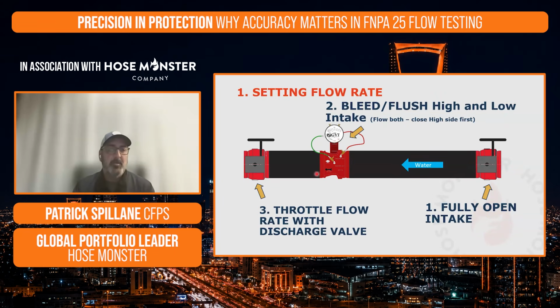But the way that we're going to set this flow meter up is that we're going to open up this intake valve 100%. It's going to be fully open, allowing water to fill the entire pipe diameter here. This valve is currently closed. As this valve is open, we're going to fill this entire unit with water. We're going to bleed out. There's a bleeder valve on each side of the flow meter that's going to allow any air or any debris that gets caught in those tubes.